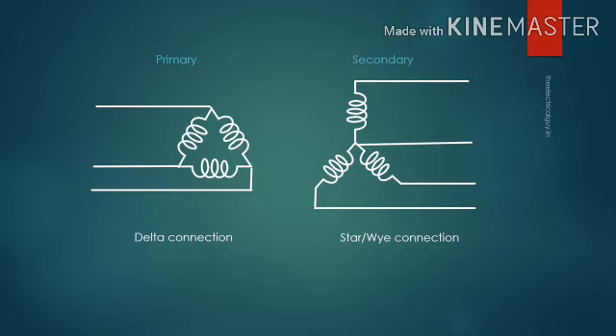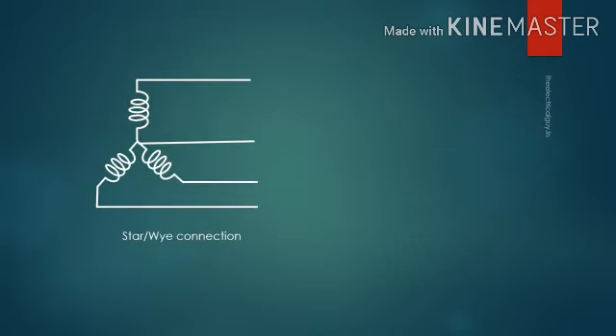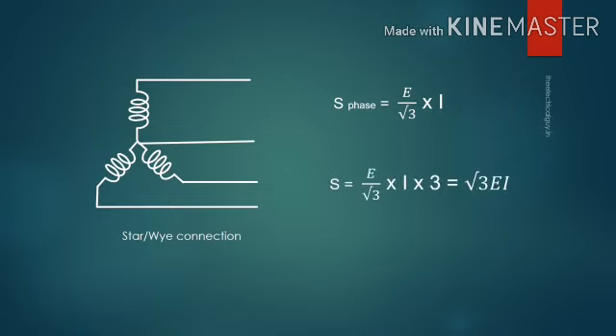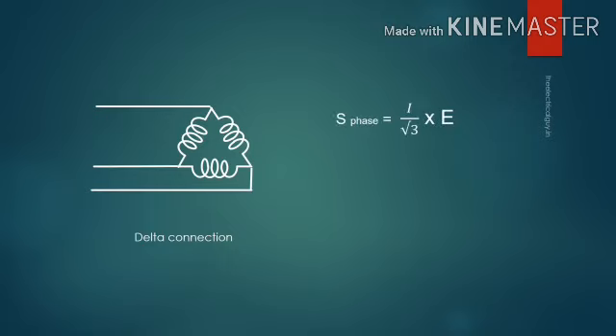Now, as we have studied the star and delta connections, a question can pop up: is the power transferred by star connection and the power transferred by delta connection the same or different? So let's find that out. Consider the star connected winding first. Apparent power transferred by a single phase is given by this formula. To calculate the power transferred by three phases, we can multiply this equation by 3. So the result will be this. Similarly, apparent power transferred by a single phase of delta connection is given by this formula. Multiply this equation by 3 to calculate the power transferred by three phases, and you will get the same result as star connection. And this proves the power transmitted by both connections is the same.